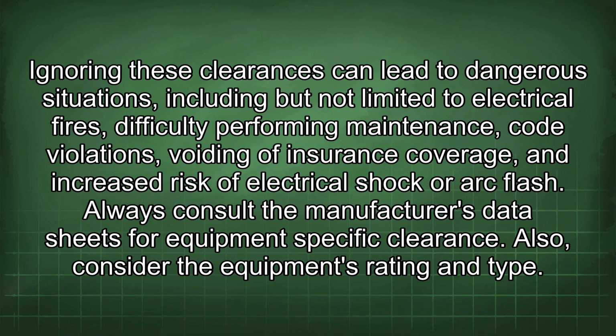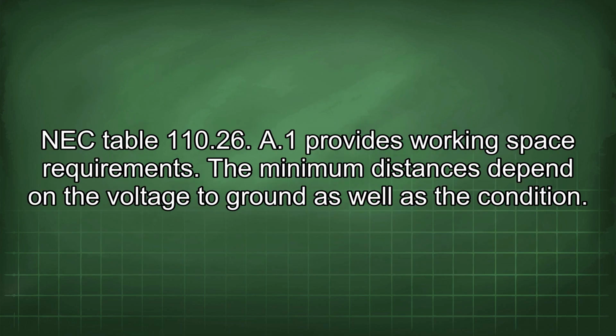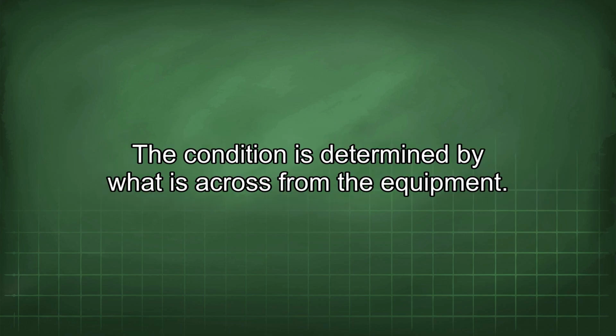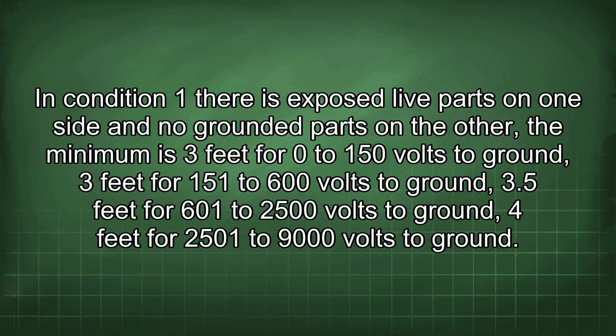Always consult the manufacturer's datasheets for equipment-specific clearance. Also, consider the equipment's rating and type. NEC Table 110.26(A)(1) provides working space requirements. The minimum distances depend on the voltage to ground as well as the condition. The condition is determined by what is across from the equipment. In condition 1, there are exposed live parts on one side and no grounded parts on the other.